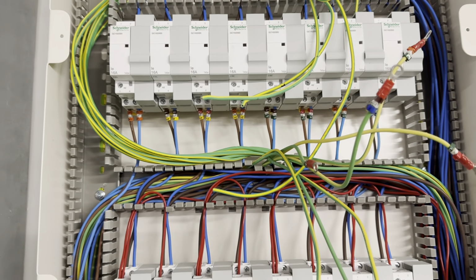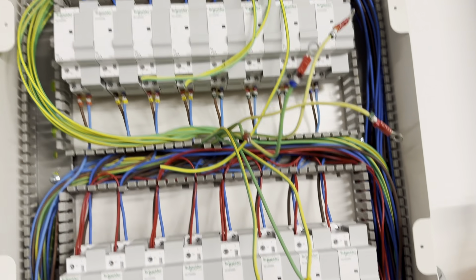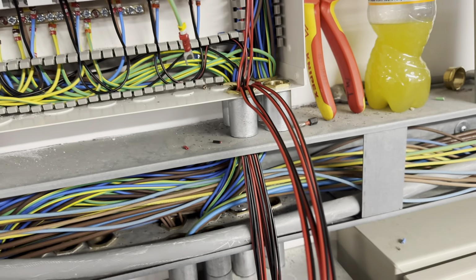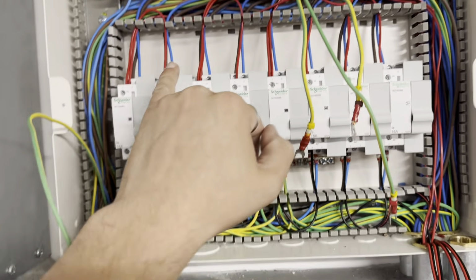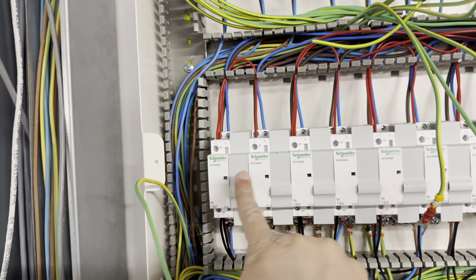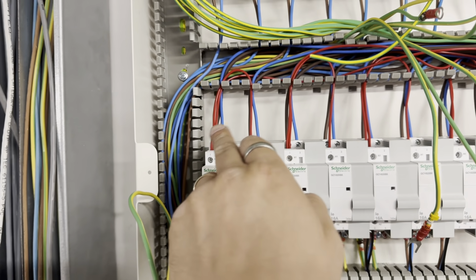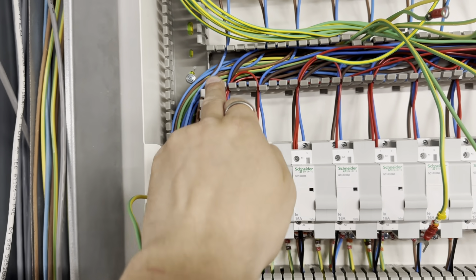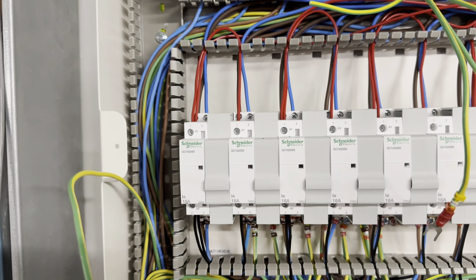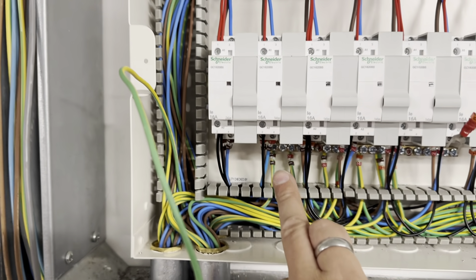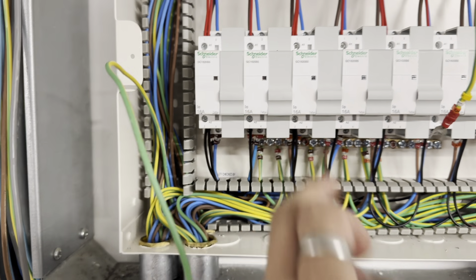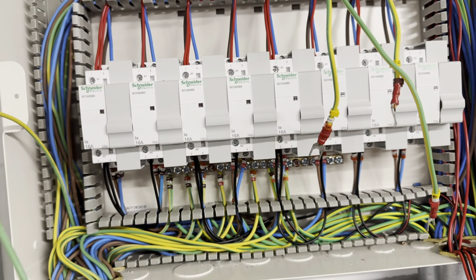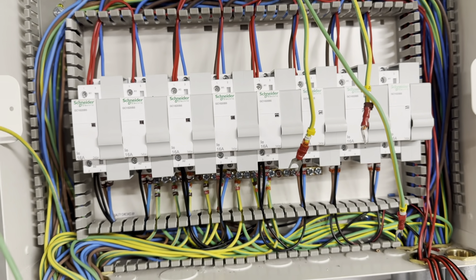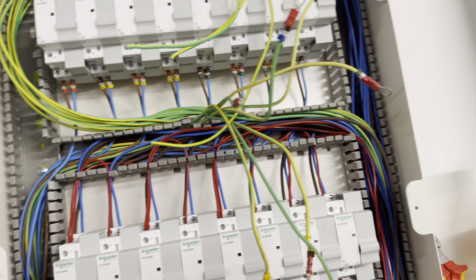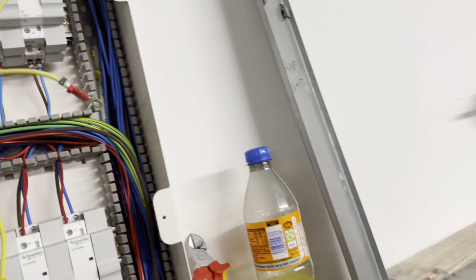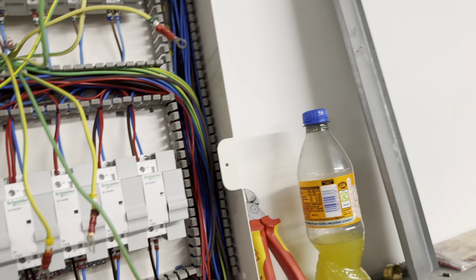I'm going to get that earth bar fitted and terminate all the CPCs, and get the last 4 24-volt control circuits up for these. One 24-volt transformer actually does 2 contactors. So you've got the 24-volt positive coming in here, and it loops across onto the A1 of the second contactor as well. A1 is always your positive or live, A2 is typically your negative or neutral, like on a 240-volt or 110 coil contactor. So I'm going to get the earth bar mounted and finish terminating, then I'll show you me mounting and terminating everything in the next board, and go through how it all functions.